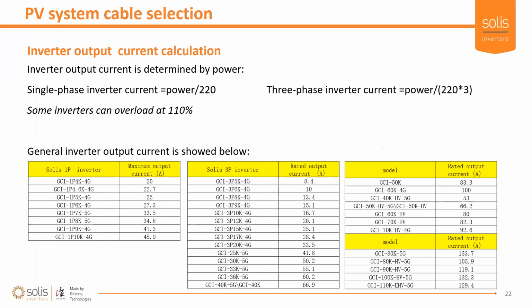Okay, so this is an example of a bad problem if you don't use that 1.25 factor. If you design your cable to handle that 10 amps, you will need to put a circuit breaker on there that trips at 10 amps or lower, so 9 amps or 8 amps. And in the middle of the day when that system's generating, you're going to get that inverter getting to 10 amps per phase, and it's going to trip that circuit breaker because it is rated at 8 amps, and you're going to get no grid alarms on the inverter. So always consider that factor that we multiply by 1.25, so you would get 12.5 amps, and then you can design your circuit breaker at 11 amps or 12 amps, just so that it's above the maximum power that your inverter can inject.